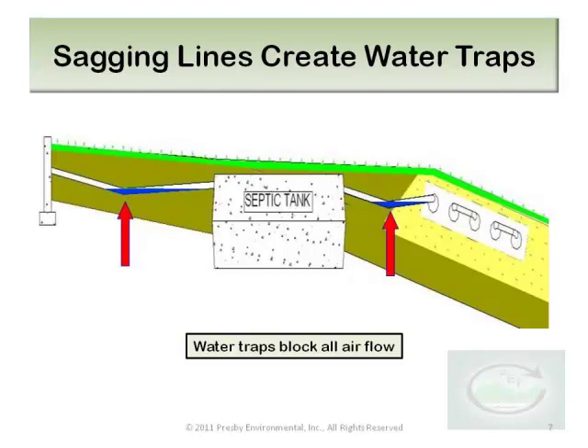During installation, try not to over-excavate your ditches and be sure to compact the soils under the sewer lines. I would also add that even though sewer and drain pipe is allowed in most locations between the tank and field, I would recommend using glued Schedule 40 PVC. This is cheap insurance against a crushed line and will help resist any potential sagging.